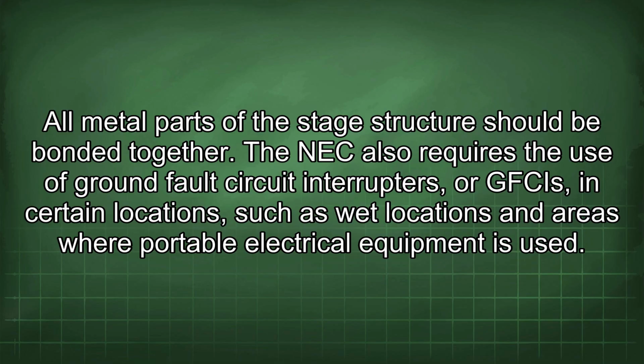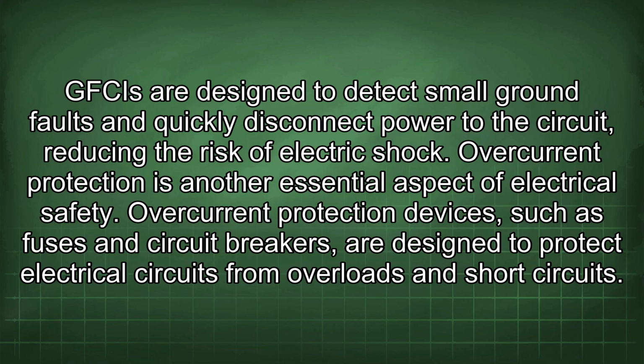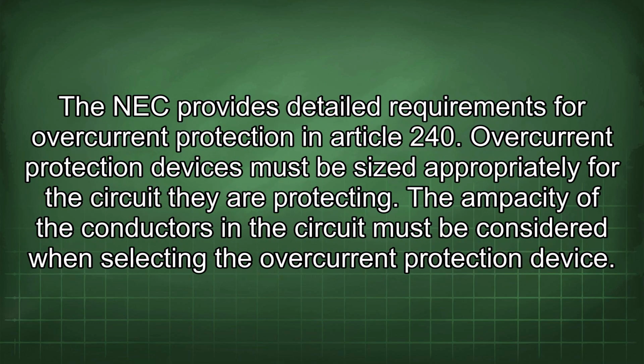The NEC also requires the use of ground fault circuit interrupters, or GFCIs, in certain locations, such as wet locations and areas where portable electrical equipment is used. GFCIs are designed to detect small ground faults and quickly disconnect power to the circuit, reducing the risk of electric shock. Overcurrent protection is another essential aspect of electrical safety. Overcurrent protection devices, such as fuses and circuit breakers, are designed to protect electrical circuits from overloads and short circuits. The NEC provides detailed requirements for overcurrent protection in Article 240.